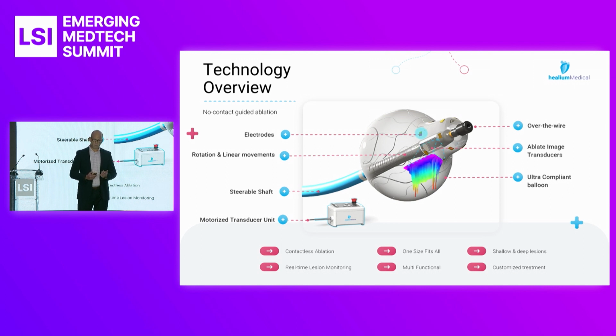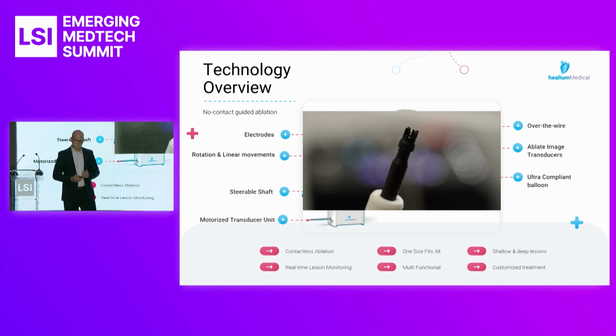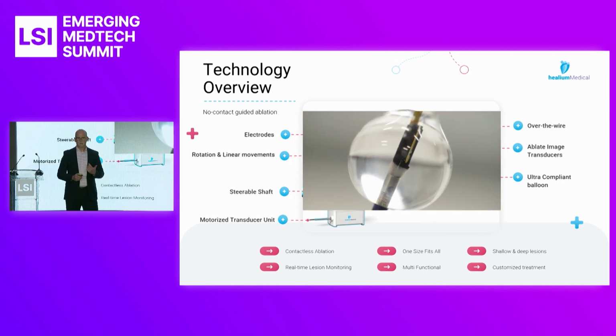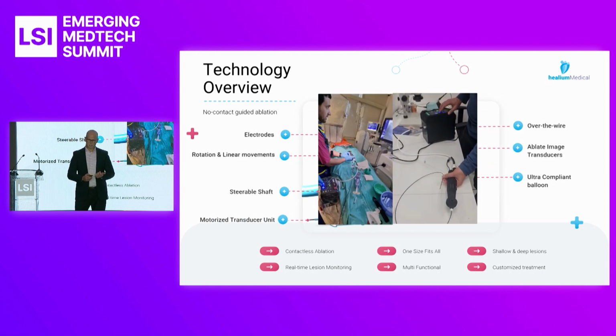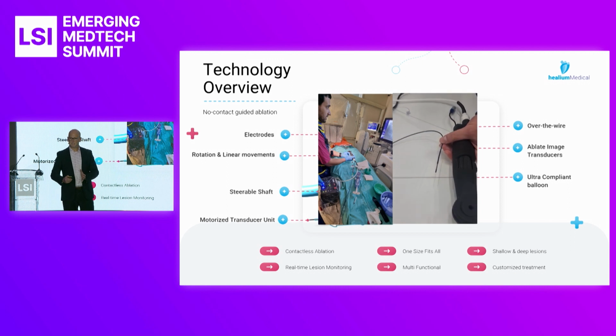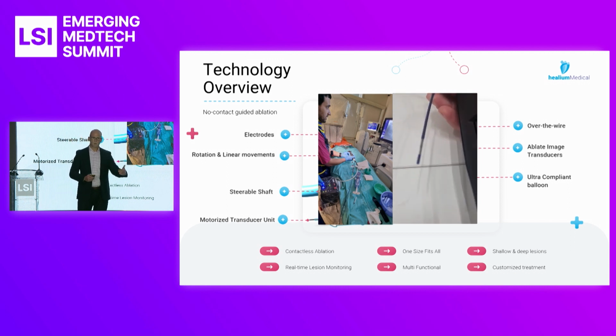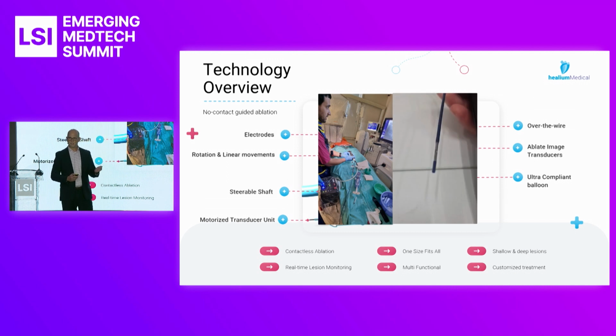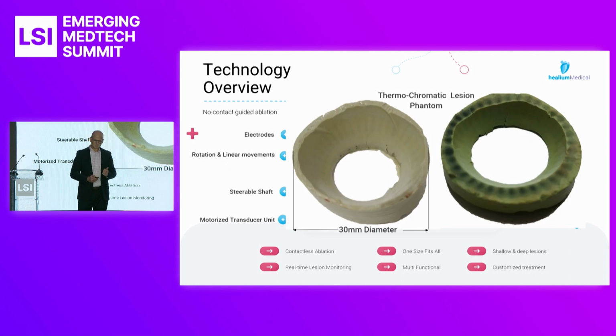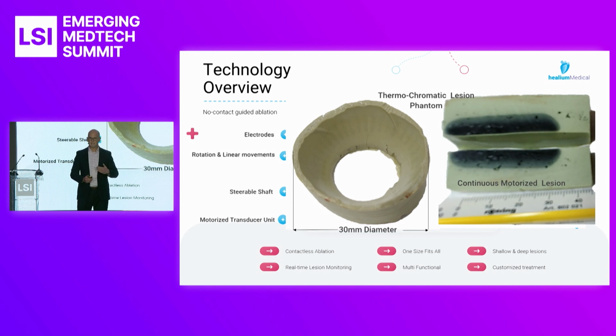Once you're ready to ablate, our transducer can do 2 things. It can ablate, and it can also image at the same time. So once you're ready to ablate, you get a very collimated acoustic energy to precisely ablate only the tissue of interest. You connect the transducer into the handle, rotate, and can create either continuous or point-by-point ablation or segmental ablation based on the anatomy. The way it looks in the lab, it's connected bedside, and we can rotate fast for imaging. We can rotate slowly for ablation, either step-by-step or continuously. When we use a thermochromatic lesion phantom, you can see how controlled the step-by-step lesions are that we create, but obviously we can also rotate continuously and get a continuous lesion.